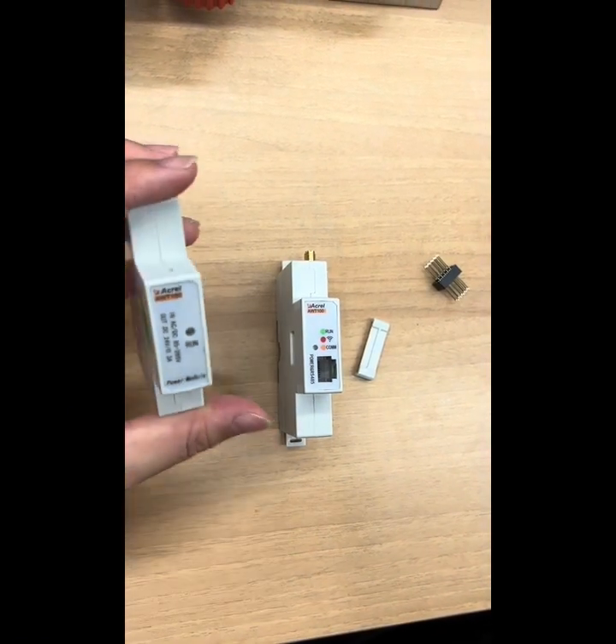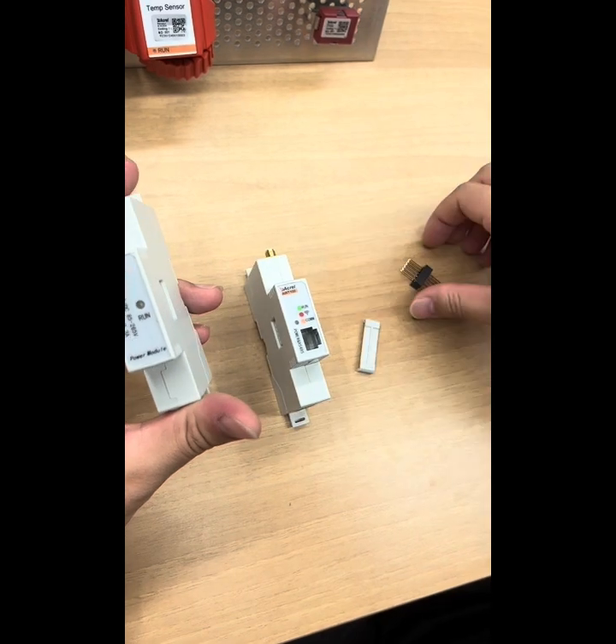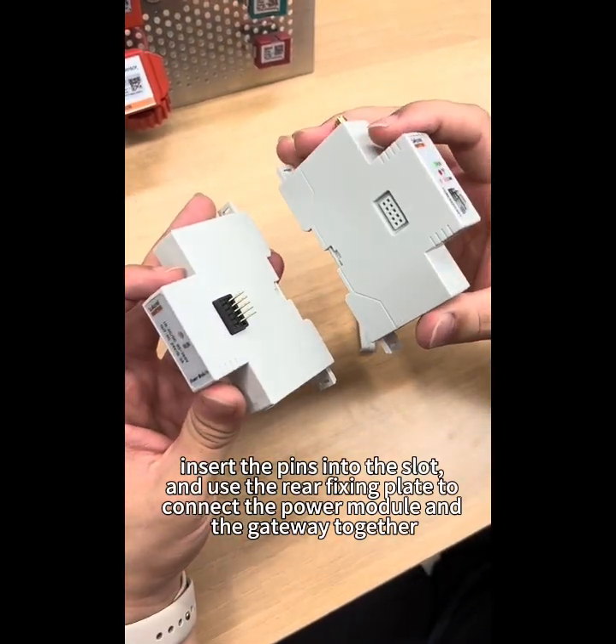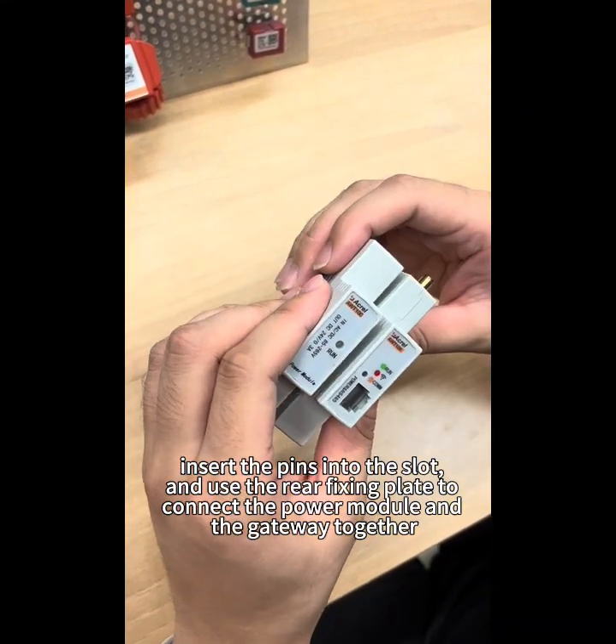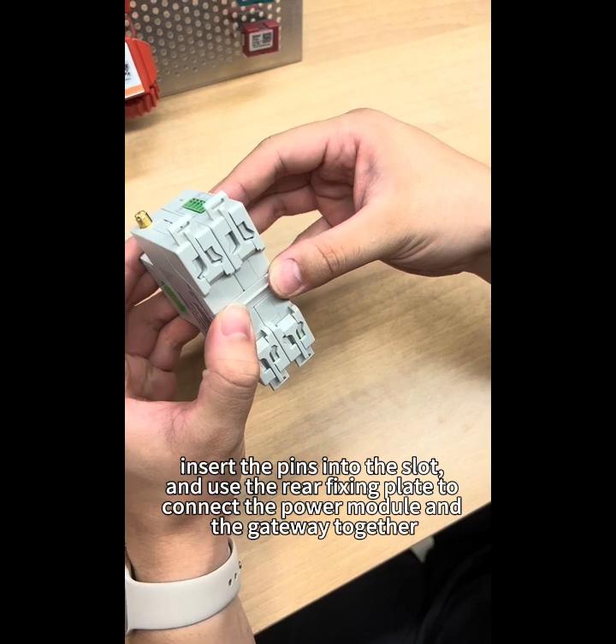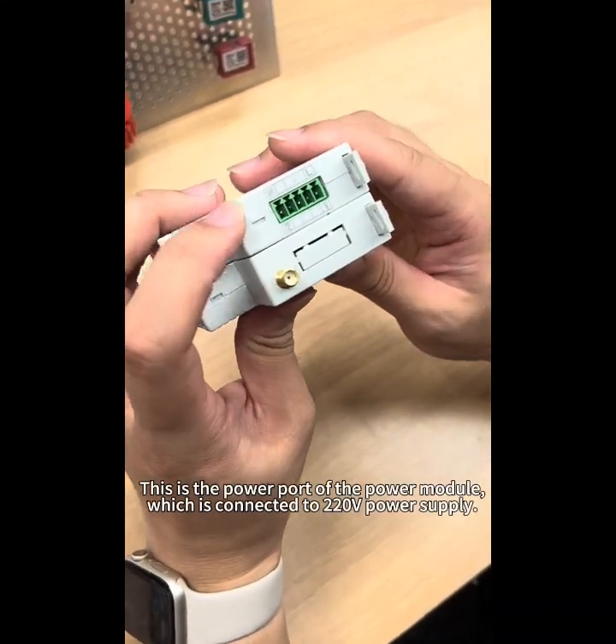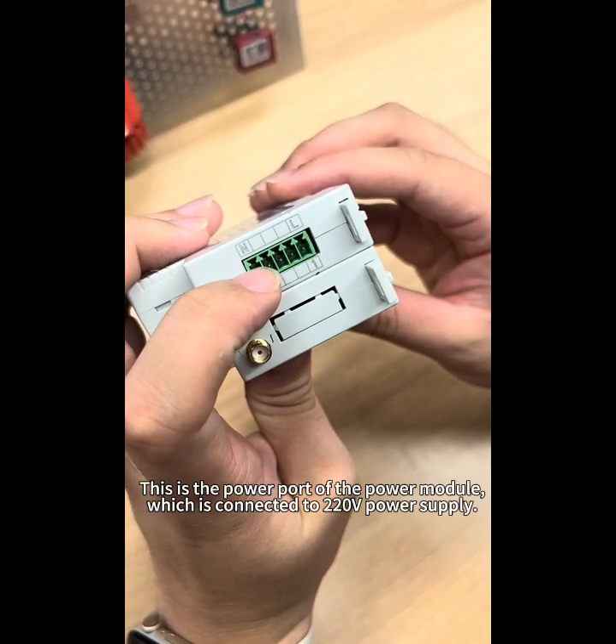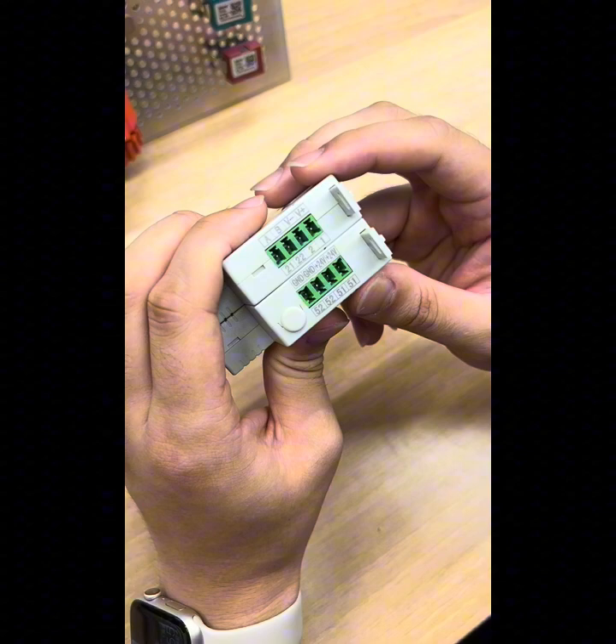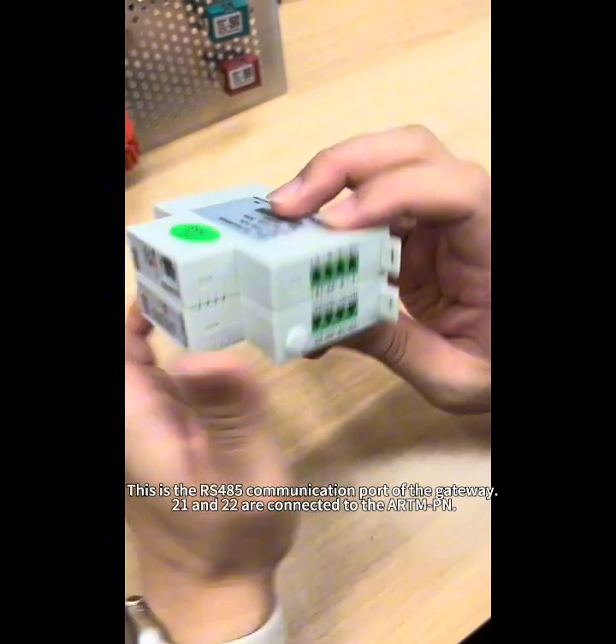How to install the gateway. This is the power module of the gateway, and this is the AWT100 Wi-Fi gateway. Insert the pins into the slot and use the rear fixing plate to connect the power module and the gateway together. The power port of the power module is connected to the 220V power supply. The RS485 communication ports 21 and 22 on the gateway are connected to the ARTM-PN.